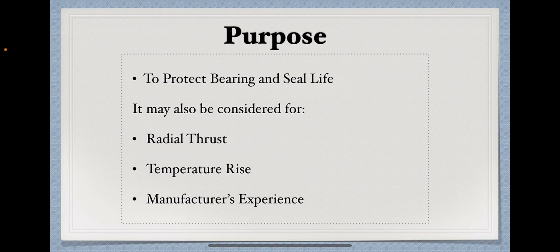The purpose of the minimum recycle is to protect the bearing and the seal life. It may also be considered for the radial thrust occurring at the pump or the increase in temperature of the pumping fluid at low flows.